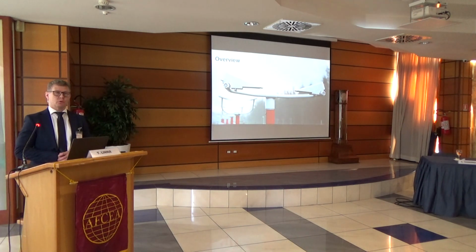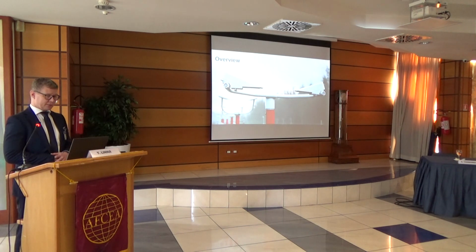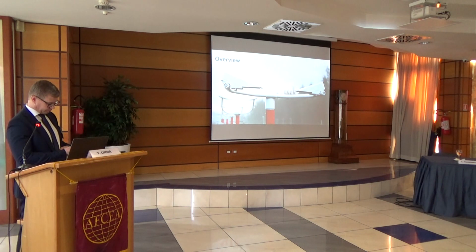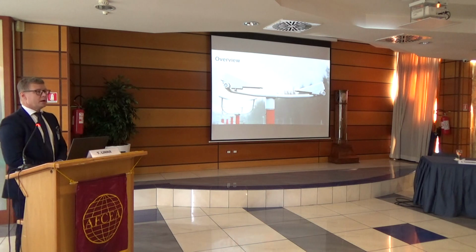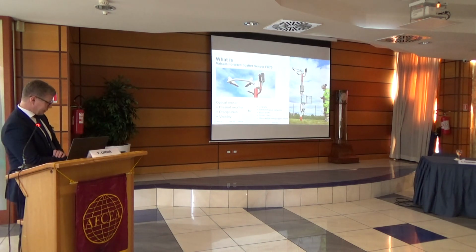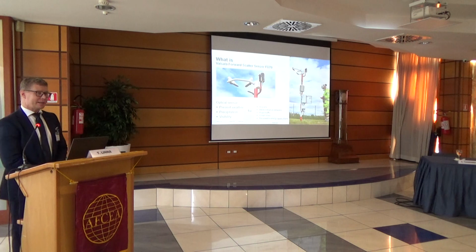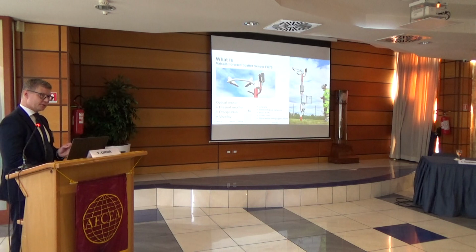Beginning from the overview. So it is a forward scatter sensor inspired by FS11 and PWD designs, which are the predecessors of the unit. Here we have a two-headed sensor, one transmitter, the right hand part of it, and then the receiver. Depending on which features you select, it's also available as a three-headed version.